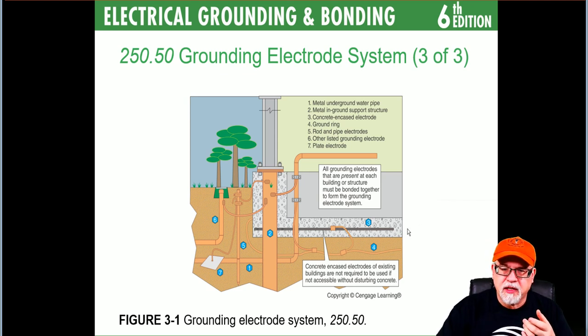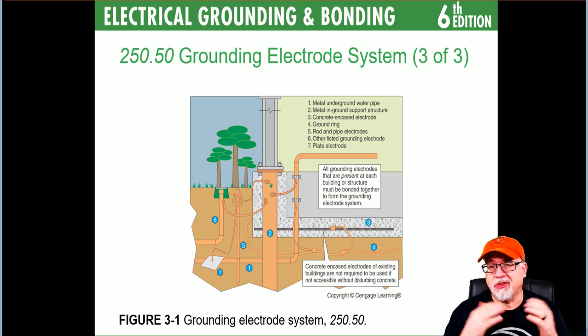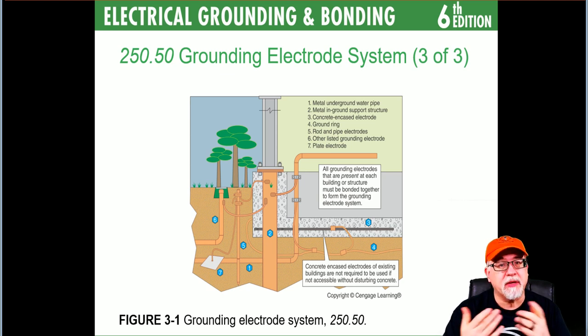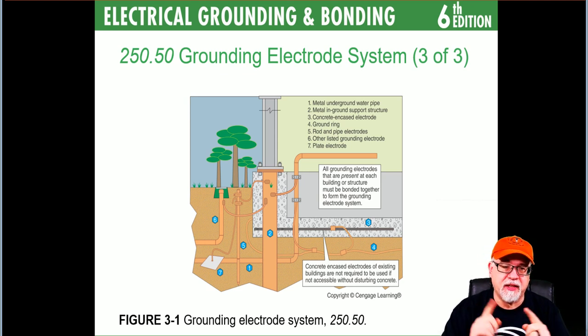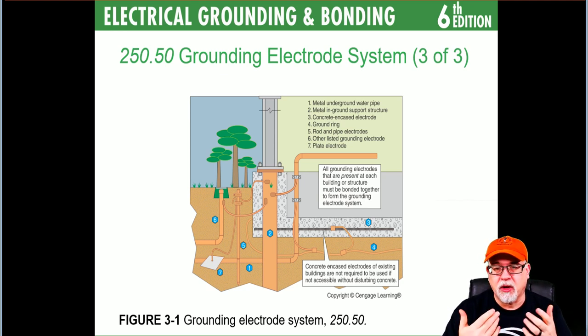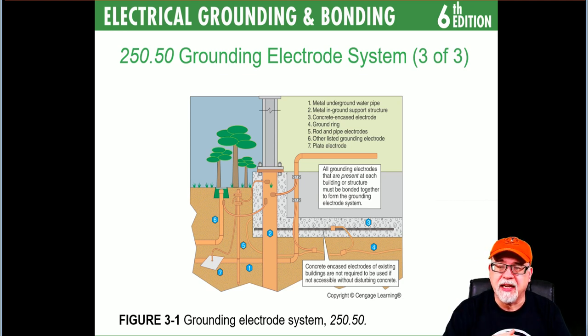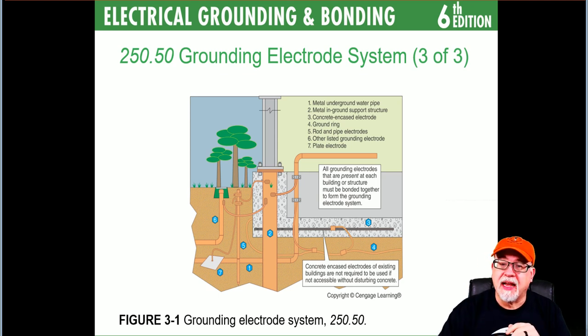Number four is the ground ring, which must go all the way around — it has to encircle the entire building. It doesn't have to be larger than two gauge, though it can be. There are some caveats in the daisy-chain effect that determine whether a larger size is needed, but typically if you have a ground ring it doesn't have to be larger than two gauge.